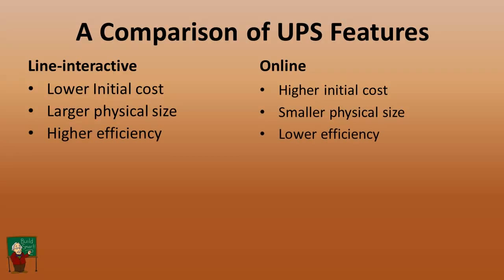Line interactive operates at a higher efficiency because most of the time the inverter doesn't have to operate. And so it can charge the batteries up and then provide very little power consumption from the unit itself. It's just passing the power through. Because it's doing less during normal operation, it produces less heat as part of that efficiency.